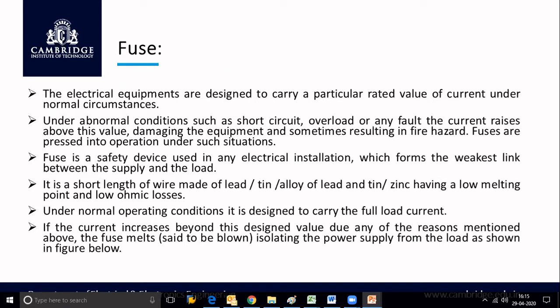Let us understand first what is meant by a fuse. The electrical equipments are designed to carry a particular rated value of current under normal circumstances. That means under normal operating conditions, all the electrical appliances are designed to carry a particular value of current. Whenever there is an abnormal condition such as short circuit, overload or any fault, then the current suddenly rises above this value. So this rise in current damages the equipment and sometimes results in fire hazards also. Therefore, we require protection of all our electrical appliances, and this protection is mainly provided by the most important protective device called fuse. Fuses are pressed into operation under such conditions.